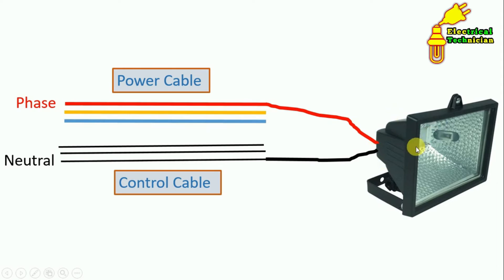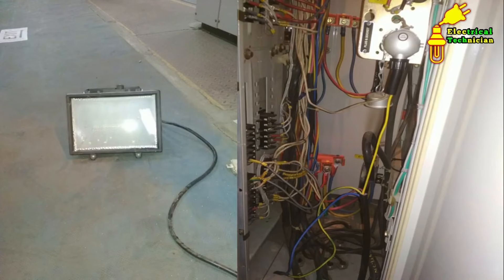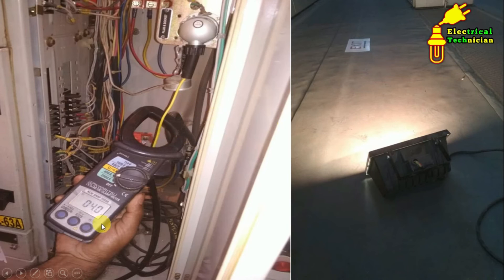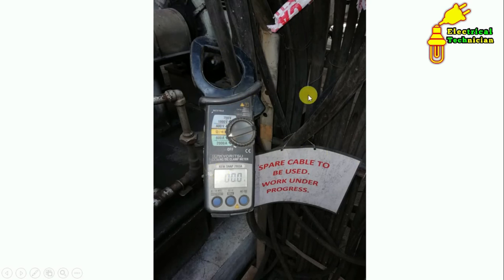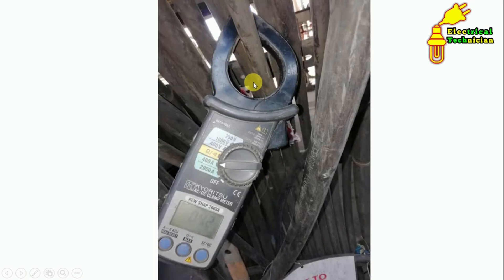We have to provide phase supply and neutral supply to the halogen lamp, and it must be through two separate cables. First of all, we measured the current at the source — it was showing 4A. We came to know that the halogen lamp is consuming 4A. Now at the place where we had to identify the cable, we started measuring current. We didn't measure current in all cables randomly — we used a trick. The control cable of the motor was 7-core 2.5 sq mm, so we measured current in cables matching that thickness. Similarly, the power cable was 3-core 16 sq mm, so we measured current in cables of that thickness. When we measured current in this cable, it was showing zero ampere. But when we measured current in this cable, we got a value of 4.2 ampere.